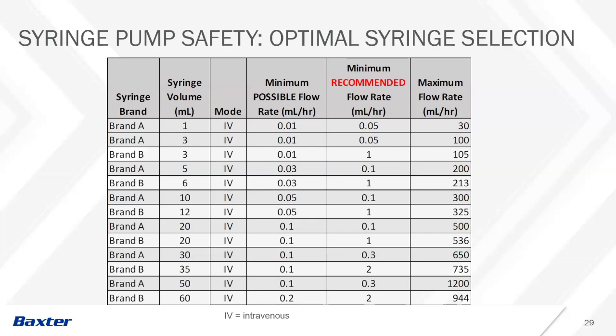This chart is an example of two different brand syringes, A and B. If you compare brand A's 3 ml syringe with brand B's 3 ml syringe, you see similar minimum possible flow rates, but different minimum recommended flow rates. This becomes a critical consideration when selecting syringes for continuous infusions running at very low rates.